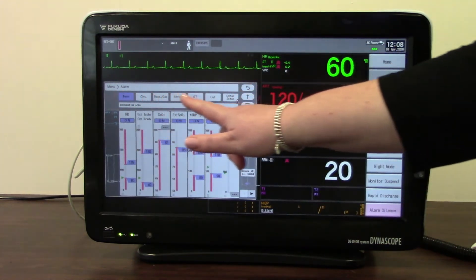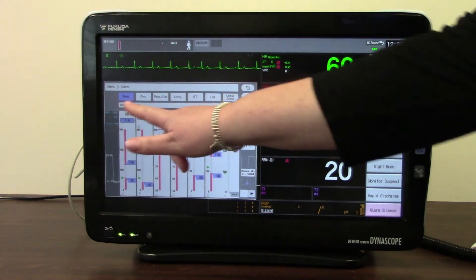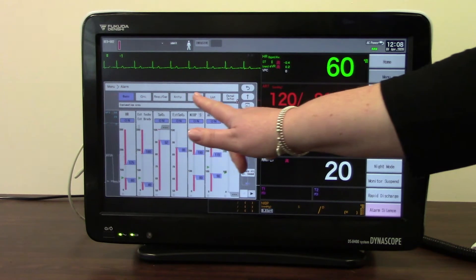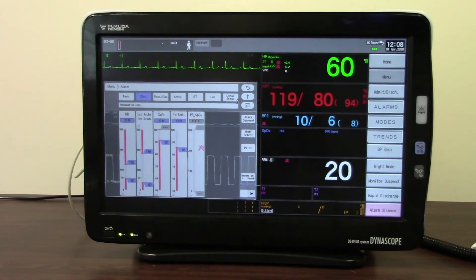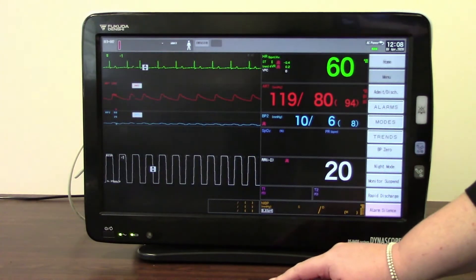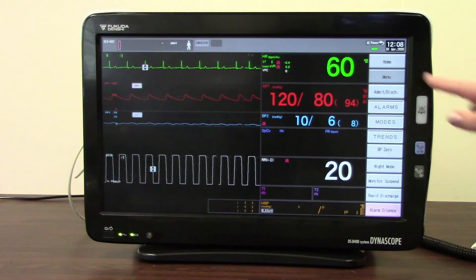You may also notice a little workflow that's opened up along the top — in here is arrhythmia alarms, which we'll come to in just a moment. I've also got every type of alarm available, so I could go into all of my circulatory alarms and page across to set any of those. The other way to set alarms is via the menu.